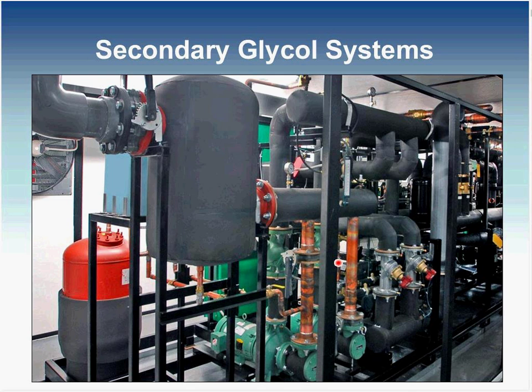If a customer is interested in spending some additional dollars in supplying leak detection equipment, there's a lot less cost to it. You can put your leak detection equipment basically in this one room instead of having to buy enough leak detection equipment to put it all across the sales floor. As Travis indicated, glycol can also be applied to distributed systems, so you can have a smaller amount of refrigerant out in your store. And there's also modular systems, which use a lot of small chiller packages run in parallel, so that gets you even to a tinier amount of refrigerant in each specific system.